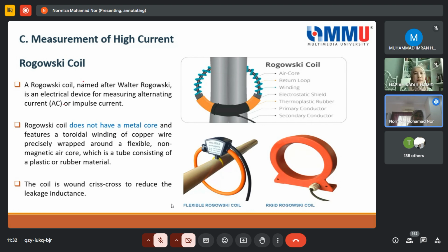where it is measuring AC or impulse, and it does not have a metal core. This is just a toroidal winding of copper wire wrapped around a non-magnetic core. So this is your cable, for example, and then you have this toroidal core, and it induces the voltage. Therefore we know that the current is proportional to the voltage, and then it gives the current reading.